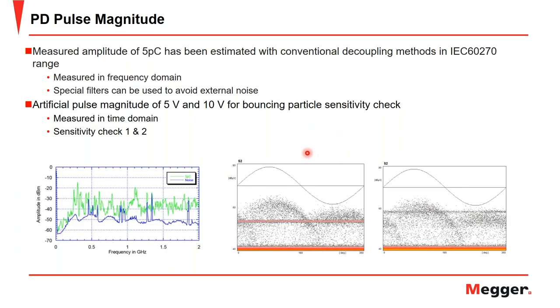So then the second part of the sensitivity check is done during commissioning of the GIS, where, once commissioned, you would inject a signal into the sensitivity check value that you found, being this 10 volts, with the manufacturer on site, and then check the surrounding sensors, checking to see if the signal can be measured on the neighboring sensors without being overwhelmed by the noise floor. So first is to create a 5 picocoulomb defect, use the conventional decoupling methods to measure this, then inject a signal that corresponds to that 5 picocoulomb value, and then on the site inject that signal that was found during the sensitivity check at the manufacturer to be sure that the signal can be seen on site.